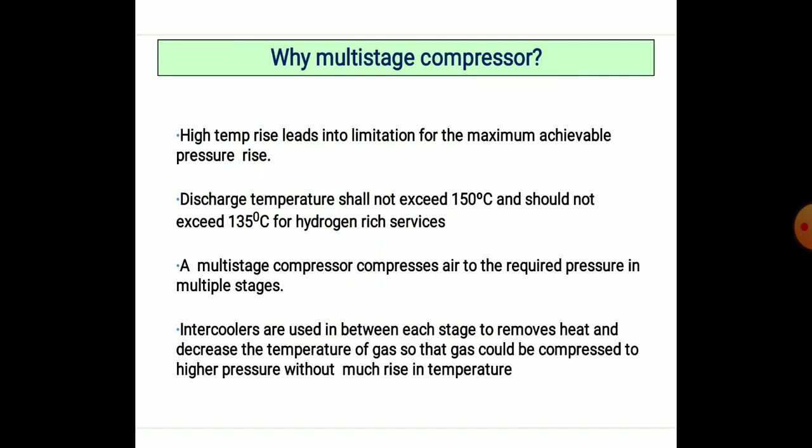To overcome all these problems, there is a requirement of multi-staging of the reciprocating compressor. Multi-staging is required because a high temperature rise leads to limitations for the maximum achievable pressure rise. The discharge temperature shall not exceed 150 degrees Celsius, and should not exceed 135 degrees Celsius for hydrogen-rich services.